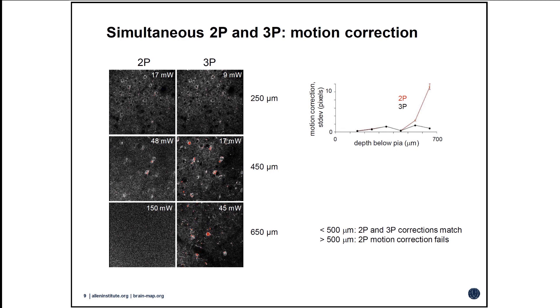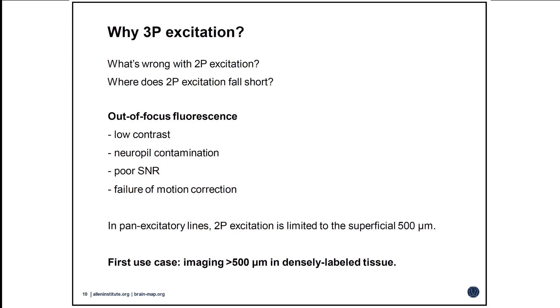At the point where contrast becomes so poor that motion correction and segmentation break, there's very little we can do with the two-photon data. For us, that break occurs at about 500 microns. So we can get to about half the depth of cortex with two-photon and then switch to three-photon microscopy. One surprise was that we actually tend to use lower laser powers for three-photon than two-photon microscopy — thermal heating was not the problem I anticipated.